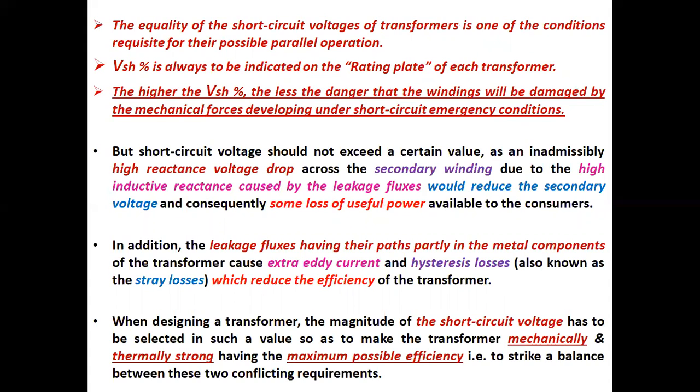The equality of the short circuit voltages of transformers is one of the conditions requisite for their possible parallel operation. VSH percentage is always to be indicated on the rating plate of each transformer. Number 3, the higher the VSH percentage, the less the danger that the windings will be damaged by the mechanical forces developing under short circuit emergency conditions.